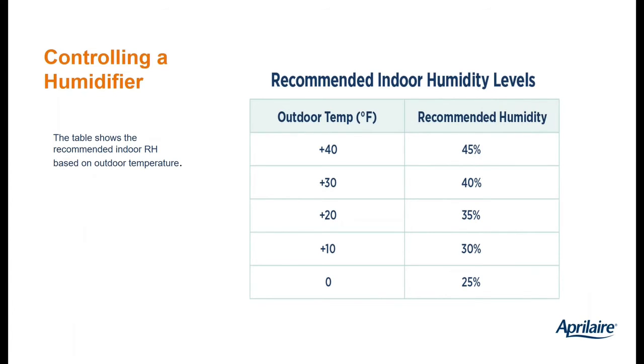We're talking about a humidifier. So in most parts of the country, we're talking about raising the humidity during the heating season. However, in the desert Southwest, we're going to humidify year-round, and in areas that have a high elevation, like Denver, we would be humidifying for much of the year. Typically, we want to raise the humidity as high as we can without getting damaging condensation. So, if we can maintain 35% in the heating season, that's excellent.